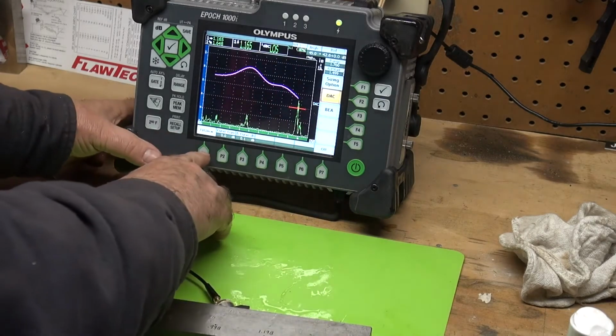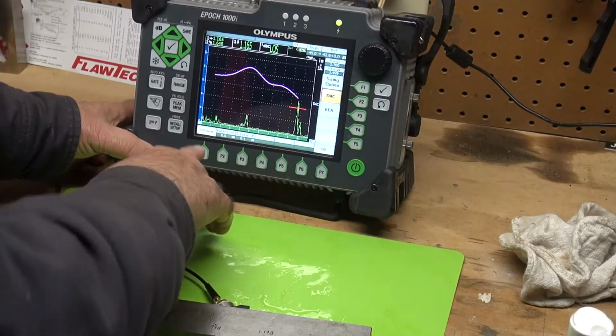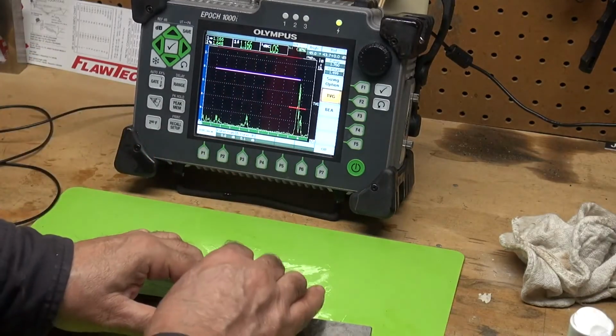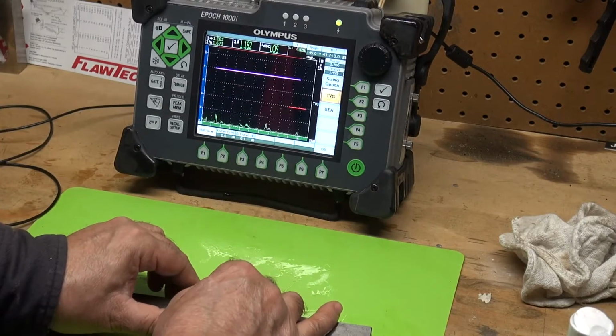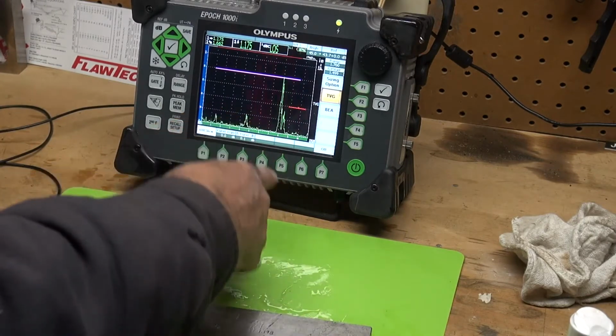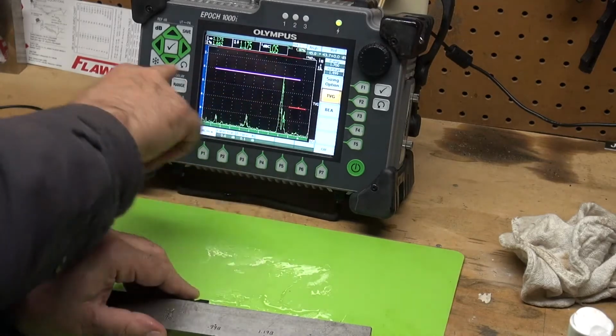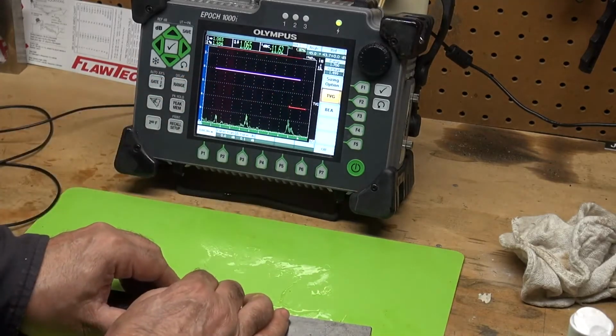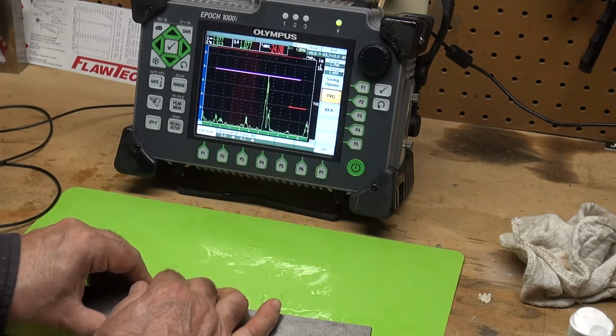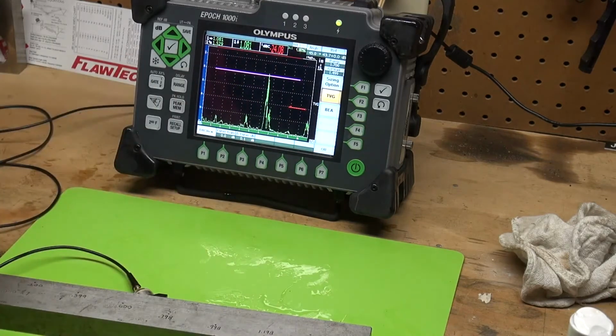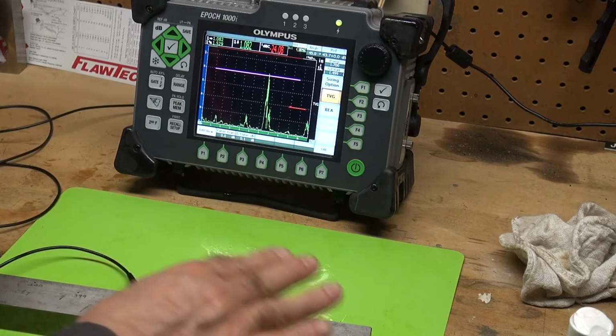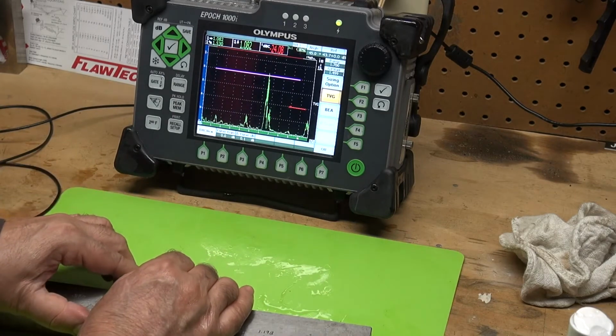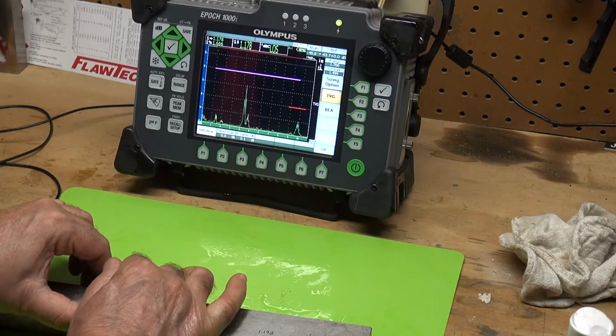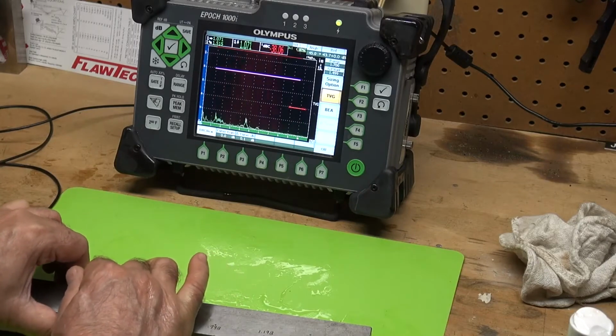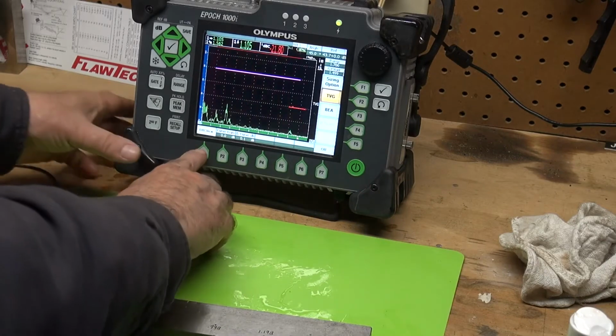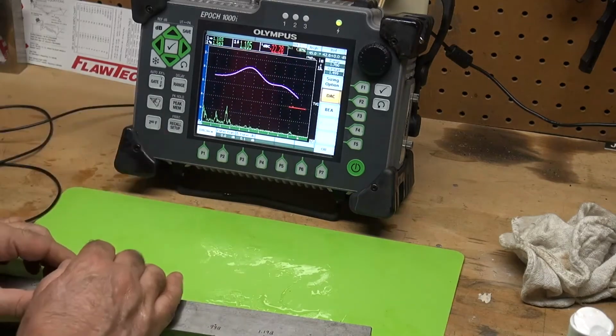Now I can also press TVG, time varied gain. It'll straighten that line out. And there's my 1.2 inch hole. There's a 1 inch hole. You'll see electronically it will move all these signals up to that level that we set with the DAC. The electronics will compensate for the gain according to the sound path. See that? Now let's go back to our DAC view, and you see that curve.